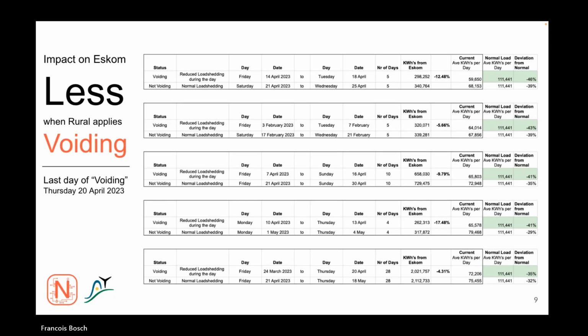Now, one would have a knee-jerk reaction to say, okay, if we don't switch off, it means we're going to use more electricity from Eskom. And this is what these figures actually show: our normal load, if we take the average of the 5 years, is 111,000 kilowatt hours per day. And there you can see that our kilowatt hours from Eskom now range from 59,000 to 79,000 kilowatt hours for the day.